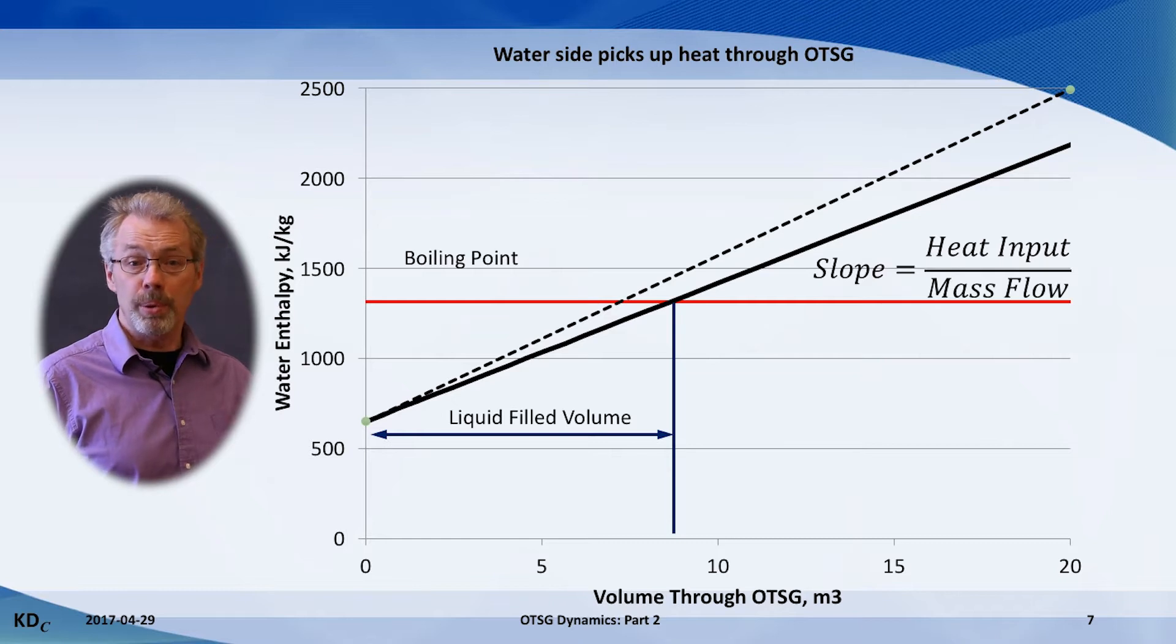Along with the OTSG producing steam with higher enthalpy and quality, the volume of water held in the OTSG also decreases. Water must be kicked out of the OTSG during this transition, which means the Venturi steam quality will read false. Part 3 will demonstrate how this plays out.